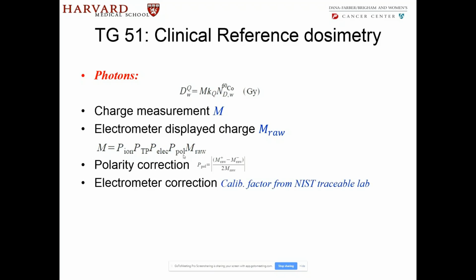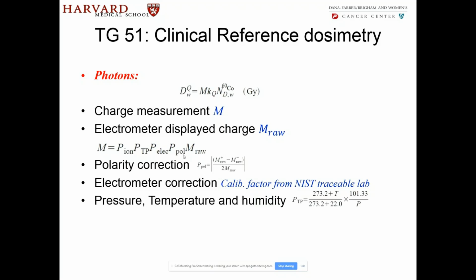The electrometer correction is basically a calibration factor. So you send your electrometer out to the NIST traceable lab. Again, you will get a factor. Usually it is 1 or very close to 1. The pressure and temperature that you have within the bunker where you're doing the measurements is what you apply.